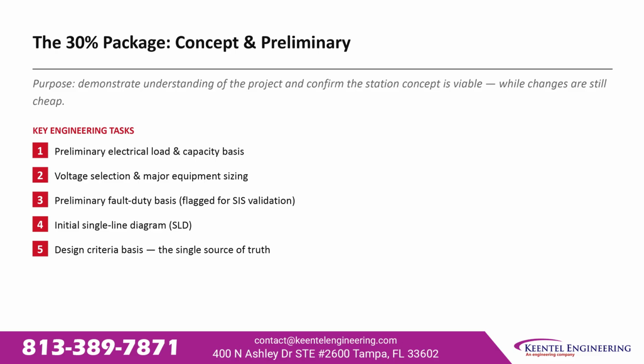The key tasks at 30% are a preliminary electrical load and capacity basis, voltage selection, and major equipment sizing, a preliminary fault duty basis flagged for System Impact Study validation, an initial single-line diagram, and the design criteria document, the single source of truth for every subsequent milestone.